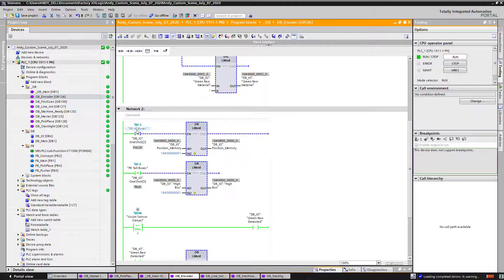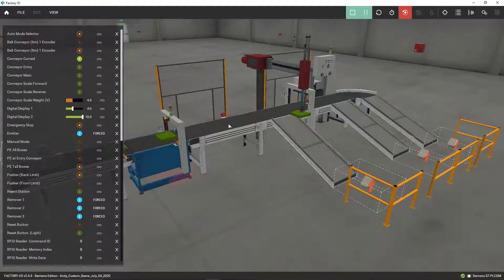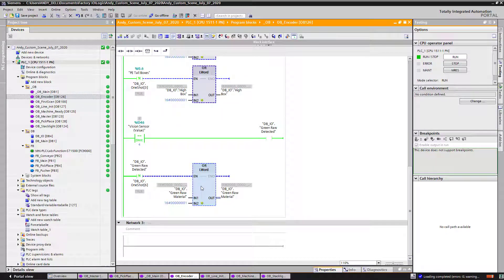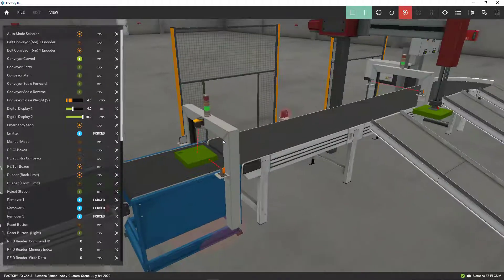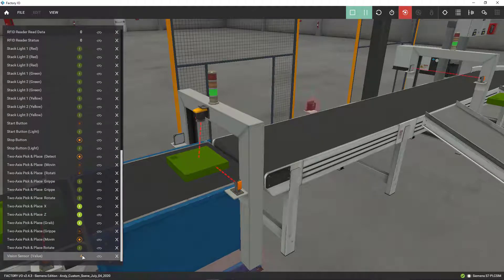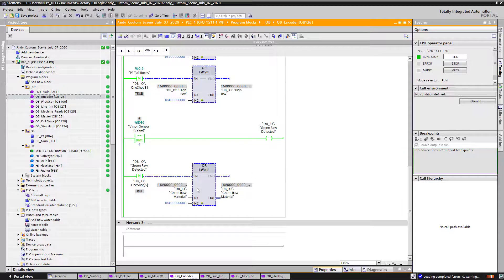This is my shift register, and every time I see a box — every single part along my conveyor — I'm going to put a number 1 on my shift register. I do the same thing when I see a tall box, and also when I see one of my green boxes. I check my vision sensor right over here. It tells me it's looking at a green part, so the value on my green sensor has to be 4. If I see number 4, I go ahead and activate this bit, which puts a number 1 on my shift register word.